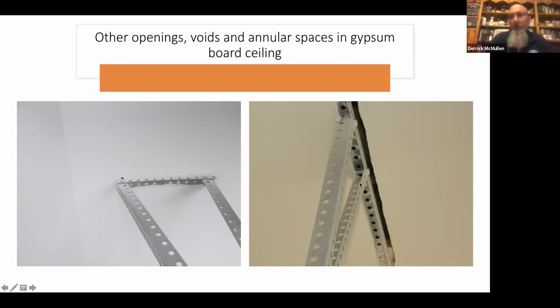There's a ceiling joist there, there's a ceiling joist there, and there was one up here. So you've got wide open spaces there. Now, technically that could just be caulked, but it would be hard to fill all that. But no openings between garage and attic space. That's a violation.